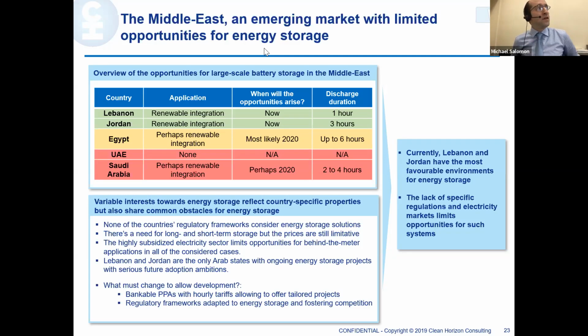Now as far as VFB, vanadium flow batteries - the big issue with vanadium flow, for those who don't know what this is: in short, this is another way to make a battery using what's called liquid electrodes. It works like a small chemical plant with two tanks filled with an energetic fluid, and when you charge and discharge the battery, you change the composition of the fluid in each tank. It's conceptually interesting because you can separate the amount of energy in the battery from the amount of power it generates. The power comes from the electronics and what's called the cell, whereas the energy is just the size of the tank, so you have more flexibility in sizing the system.